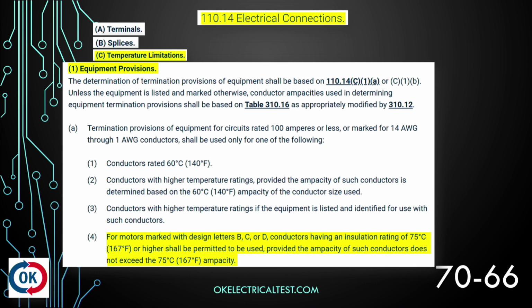So normally a 90 degree conductor can carry more ampacity than the 75. And so if I was using a 90 degree conductor, normally I would use the 90 degree column on Table 310.16. But because I'm connecting to a B, C, or D motor, and on that motor nameplate it'll say design letter B or C or D, then they're saying, hey, you can still use that 90 if you want, but I want you to size the ampacity using this 75 degree column. So this is just a piece of information that we're going to stick in our back pocket until we get to Article 430 and we're sizing conductors for motors. But if we do a B, C, or D motor, we're going to size that using the 75 degree column regardless of whether we're using a 75 degree conductor or a 90 degree conductor. Moving on, let's go to high leg marking.